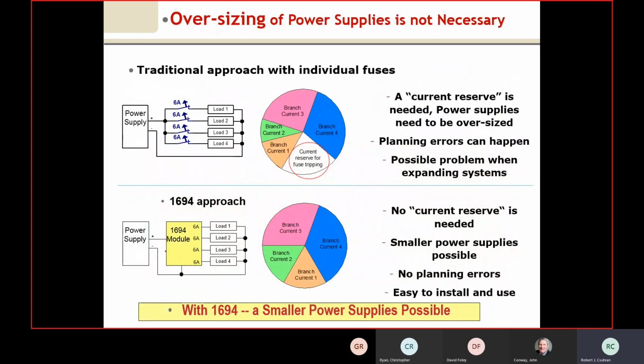If we take a look at the 1694 module, it connects to a power supply. The power supply then has a separate output for each one of the loads, and there is no current reserve needed. What will happen is if one of these units trips, the other units will stay green. The customer can quickly determine which unit has failed. This is a very efficient way to not install fuses and to find out which unit is tripped.